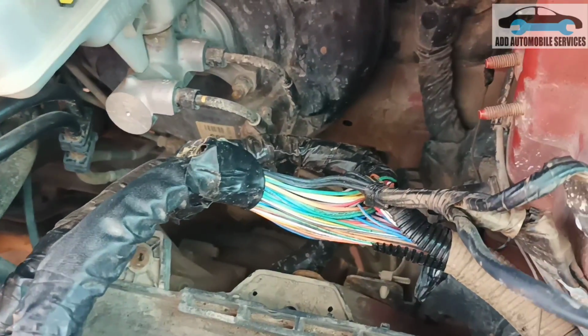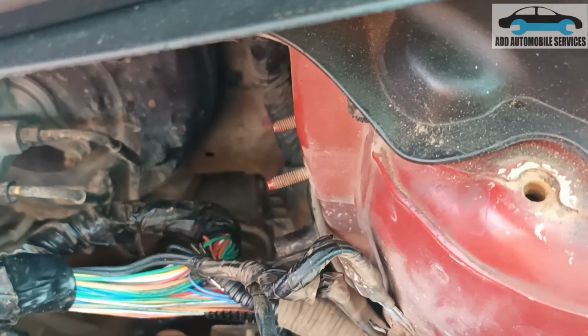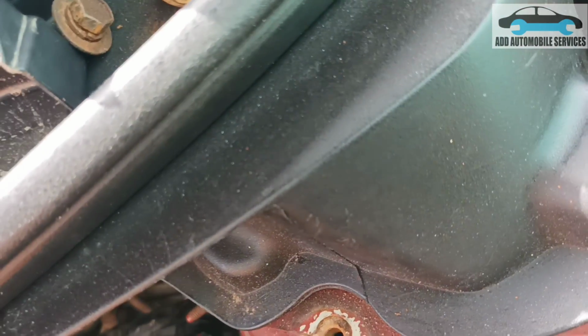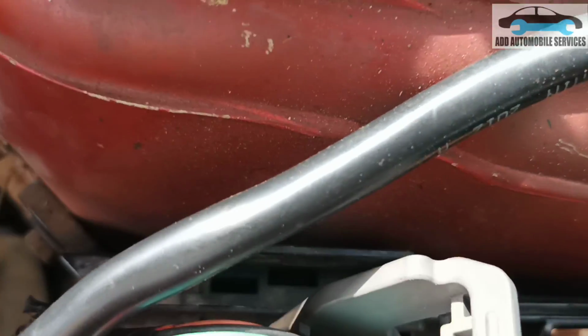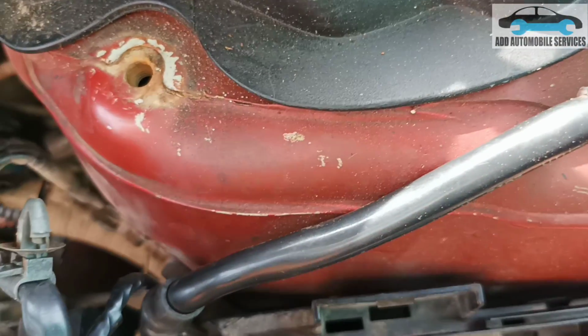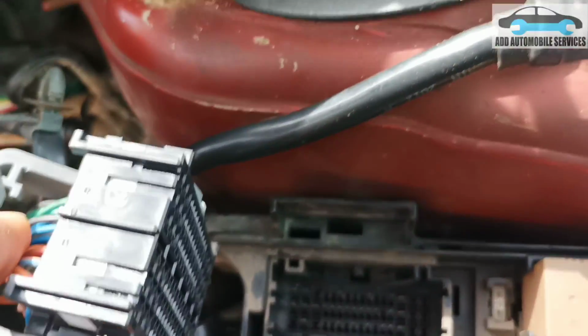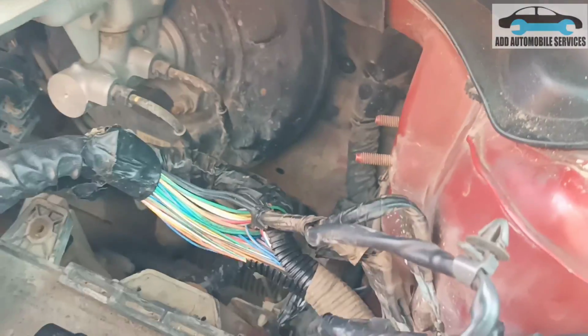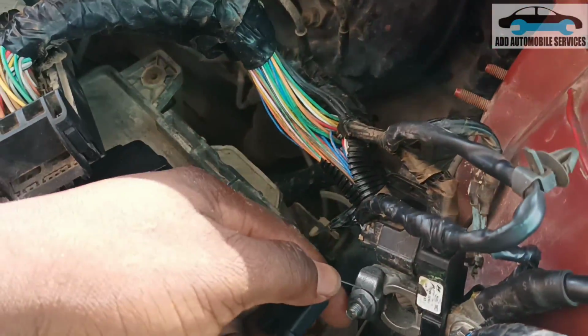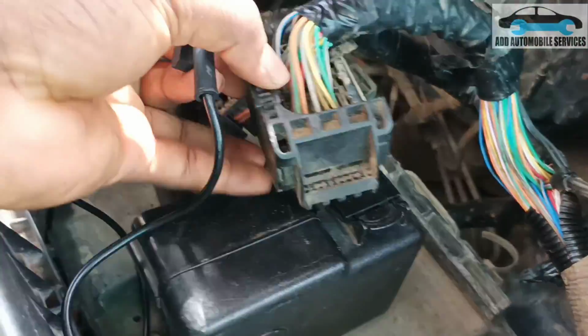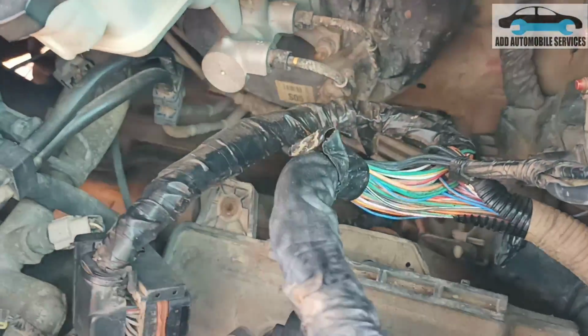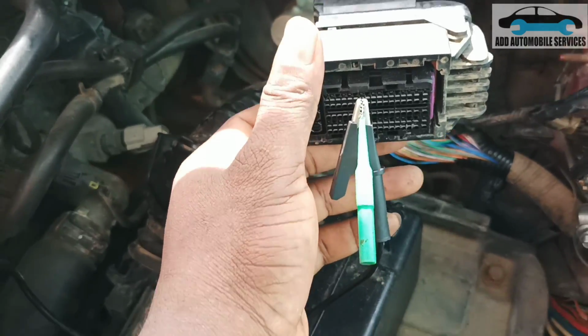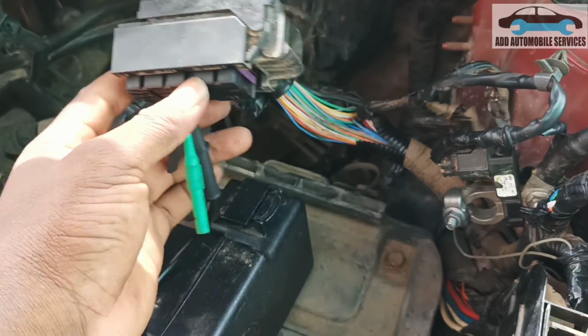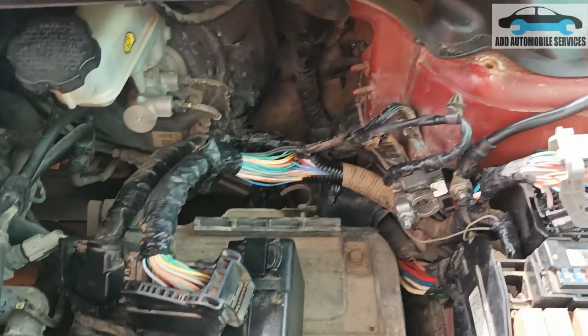So I've peeled the wire and I can't find anything so far, but normally if I pinned it here and tested it, on this orange wire, with my multimeter set to beeping, it should beep on the ground. So it is not beeping anymore. But when I bring it to the right pin, it beeps. So what I'm going to do is fix everything back and see if the fault is gone. Then I'll know what to do.